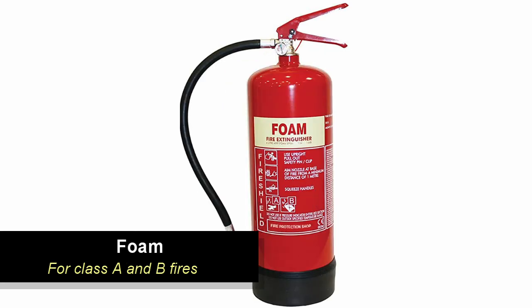Foam extinguishers work by cooling, and with liquid fires the foam forms a barrier between the fuel and the flames. They can be used on Class A or B fires. Particularly suited to extinguishing liquid fires such as petrol and diesel. They should not be used on free-flowing liquid fires unless the operator has been specifically trained, as these have the potential to rapidly spread the fire to adjacent material. This type of extinguisher is not suitable for deep fat fryers or chip pans.